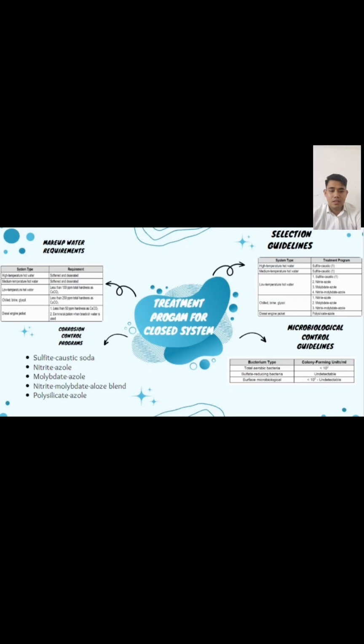For selection guidelines, system type and treatment program. For high temperature hot water, sulfite caustic. Medium temperature hot water, sulfite caustic. Low temperature hot water: number 1 sulfite caustic, number 2 nitrite azole, number 3 molybdate azole, number 4 nitrite molybdate azole. And system type chilled brine and glycol, the treatment program is number 1 nitrite azole, second molybdate azole, third nitrite molybdate azole. For diesel engine jacket, the treatment program is polysilicate azole.